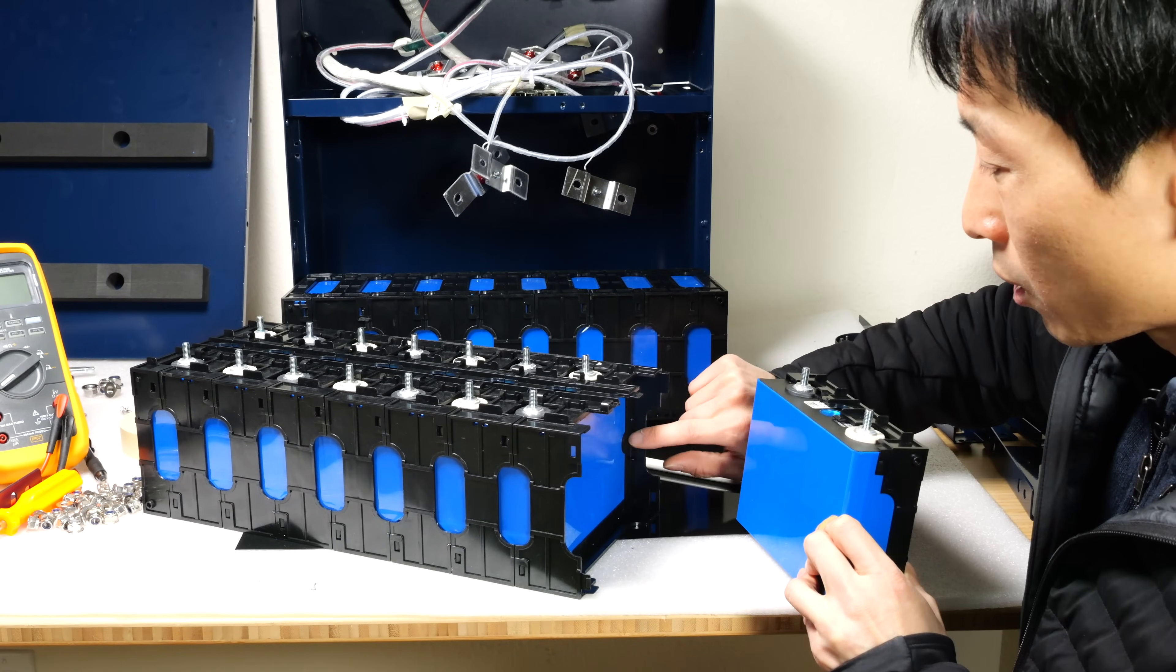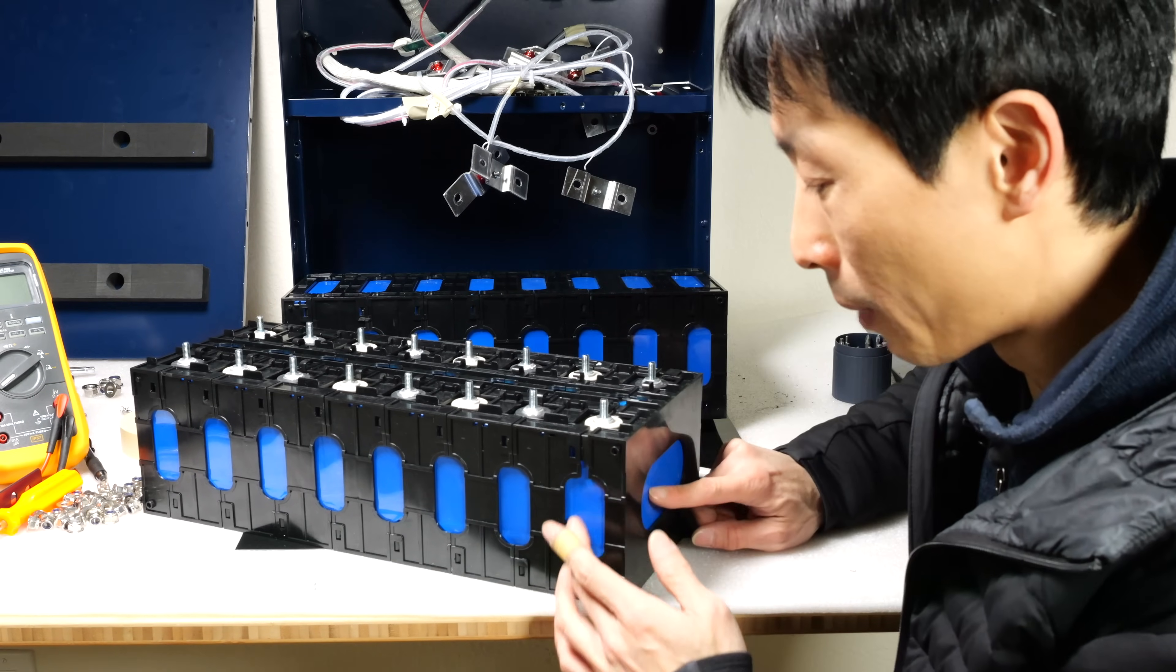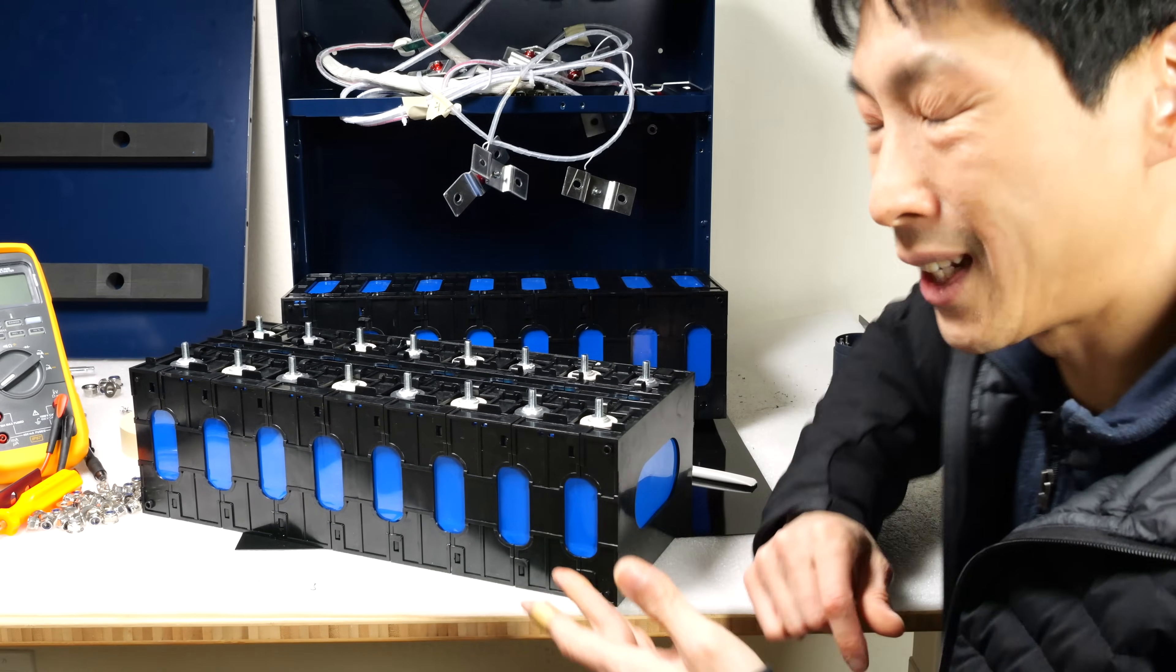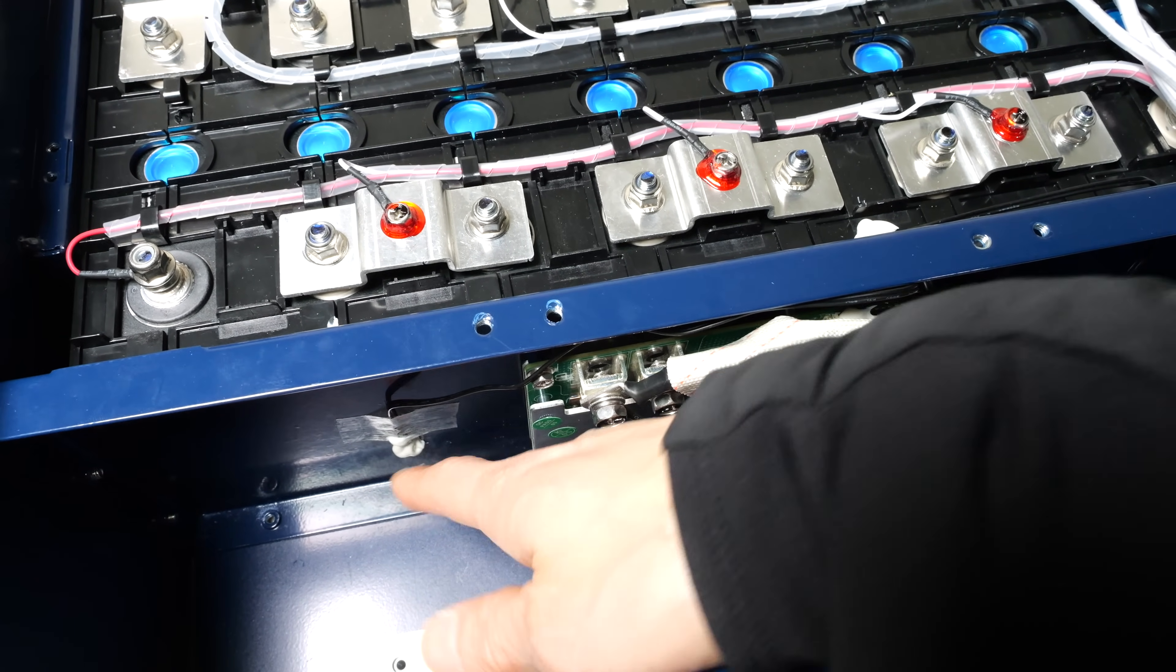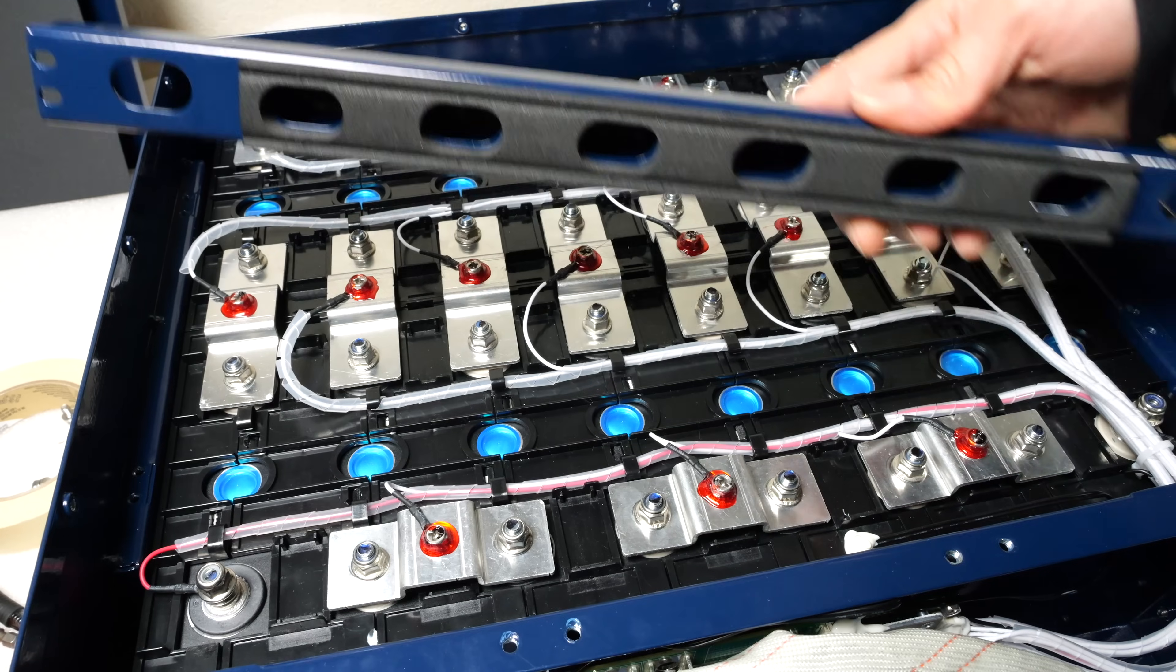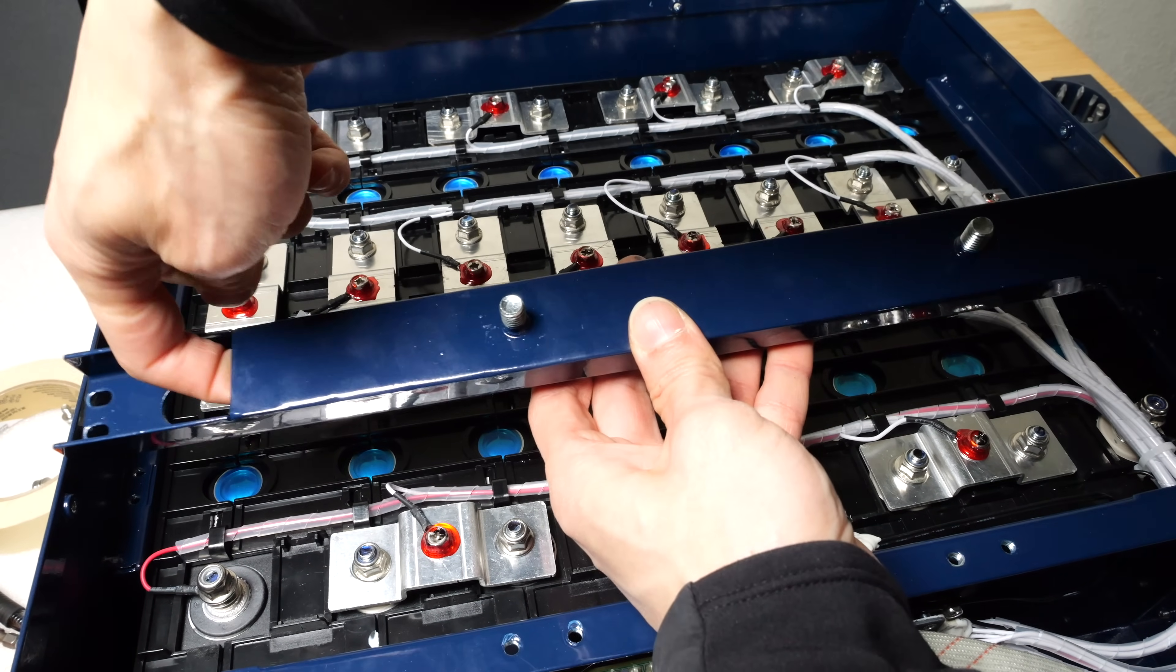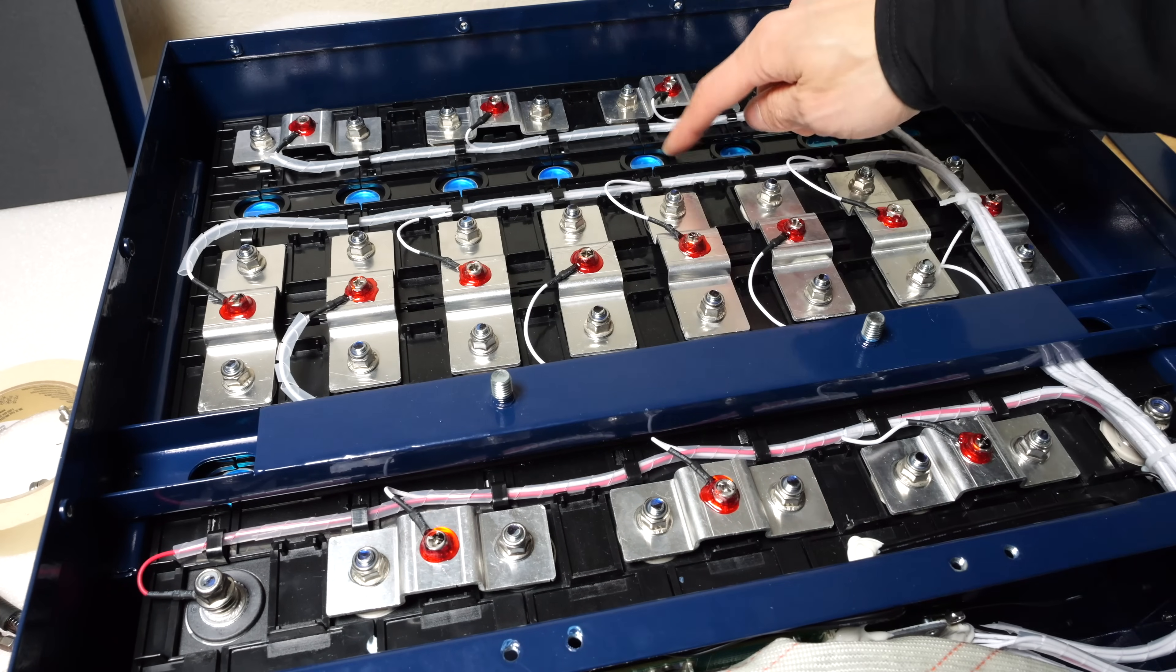There's a space between each of these batteries. A very narrow space. Let's put it back. These are vent holes. No barcode or writing or anything until you remove this, then you can see the barcode here. And all these just snap into place. It's kind of like Legos. There are two temperature sensors, one right here and one down here. Both are hot and cold sensors and these are just bi-metal sensors. There are two bars that goes across here and here and if you flip them over, it's actually a vent hole and it'll come out through here and on the other side. They take care not to cover up these vent holes.